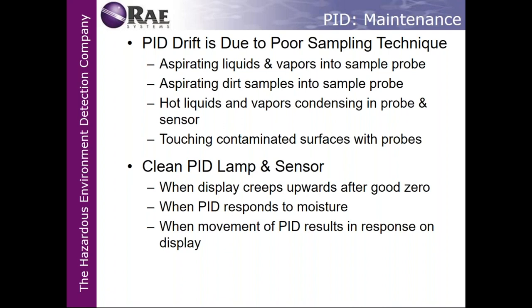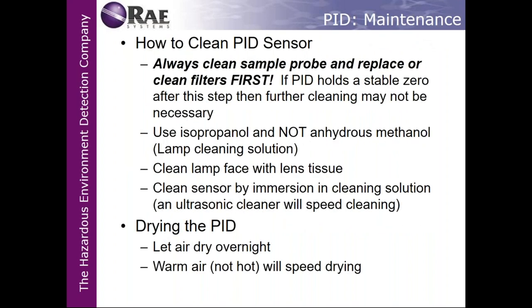When the PID responds to moisture, so usually what people will do is they'll clamp their hands around the end of the PID and let the moisture from your hand get sucked in through the PID. That also will tell you that you have microscopic dirt inside your PID that needs to be cleaned. Now, how to clean a PID sensor is really simple. Chances are, I would change your filters first. If your PID holds a stable zero after this step, then there's no cleaning necessary.